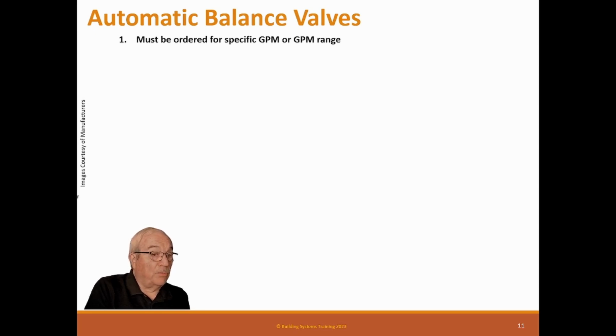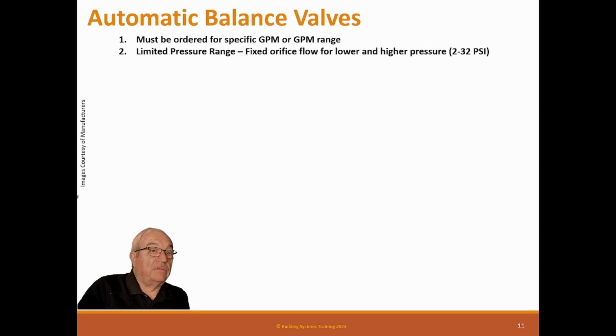And secondly, the more important thing, which most people don't realize, is that it must be ordered for a specific GPM or GPM range. You just can't take a valve and say, I've got a 3-inch pipe, we'll put a 3-inch one in there. It has to be selected for the pressure differential and the flow you want it to control. The second thing is limited pressure range. Most of these are selected from 2 to 32 psi, so if you have less than 2 psi across that valve, it's now a fixed orifice. It won't actually adjust the flow because you're out of the spring range. You haven't even started to push the spring yet. 32 psi is a maximum. If you get over 32 psi, it's pushed the spring all the way back, and now it's a fixed orifice.